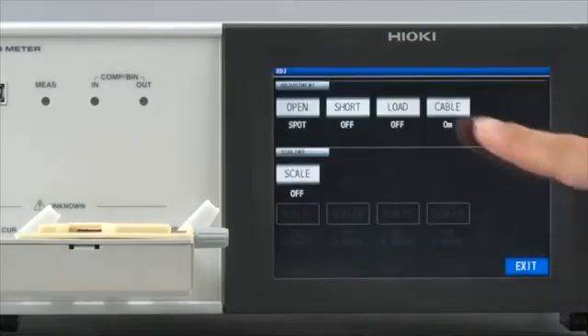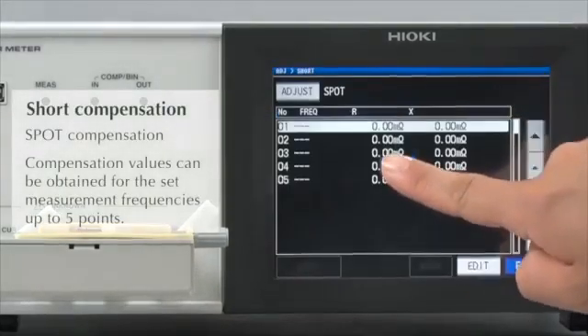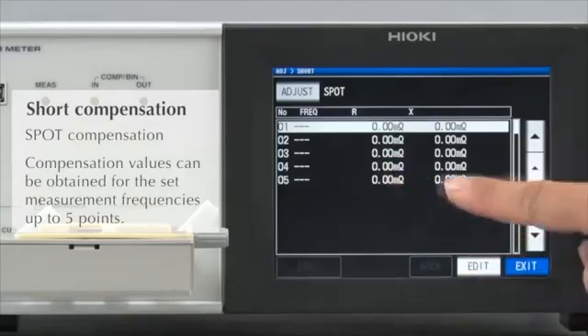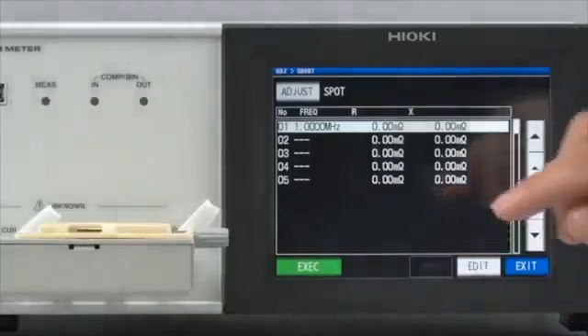Next, conduct short compensation in the same way. Set at 1 MHz. Short the fixture and then conduct compensation.